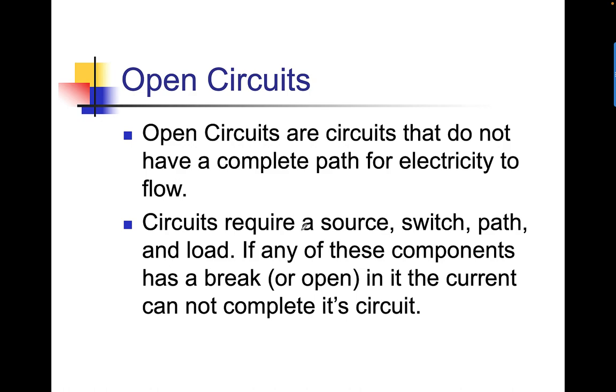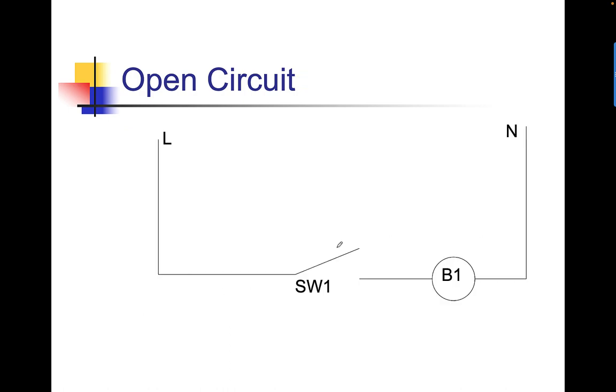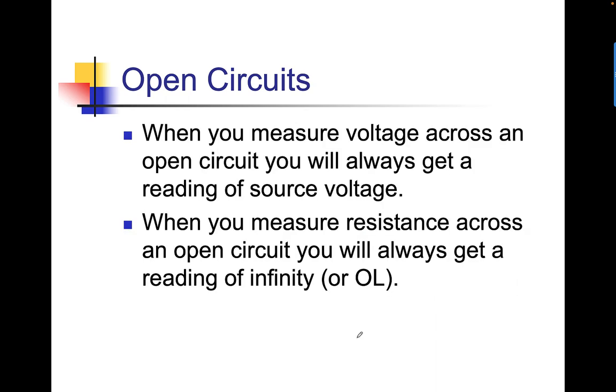Open circuits are circuits that do not have a complete path for electricity to flow. Circuits require a source, a switch, a path, and a load. If any of these components has a break or an open in the current circuit, it cannot complete its circuit. This is an example of an open circuit. See the break here where the switch is open? That electricity cannot jump across that break, so the current flow stops right here at SW1. When you measure voltage across an open circuit, you'll always get the reading of source voltage. Commit that to memory.